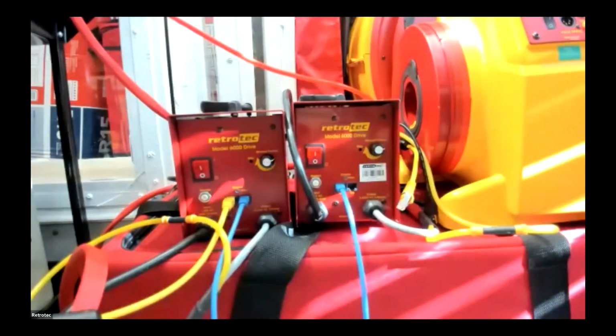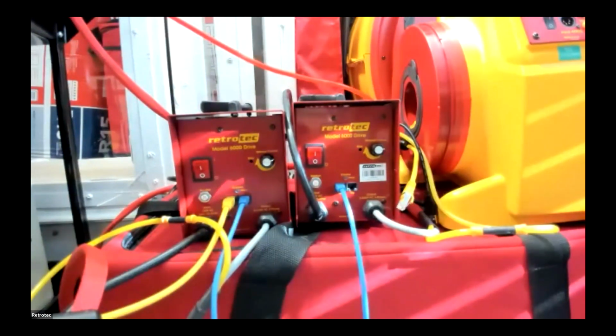So all of the drives are getting the same command from the same gauge, and they run at the same rate at the same time. This is good if you're testing one large volume of space that's not separated by a party wall or common wall. Anytime you hear daisy chain or common control, that's where we're going to do that physically.